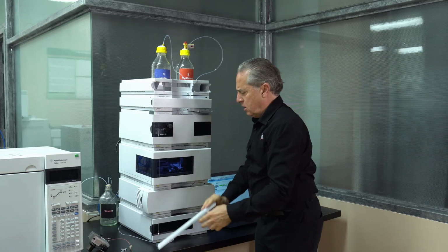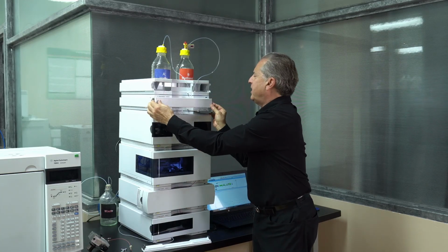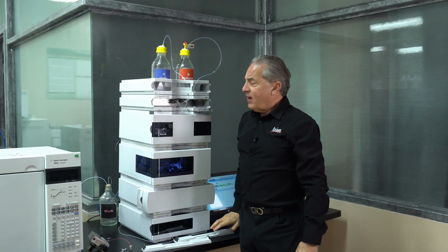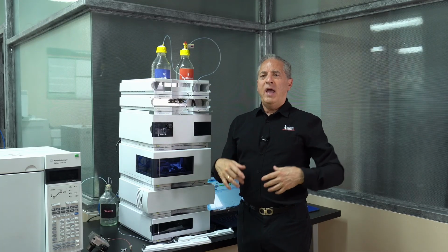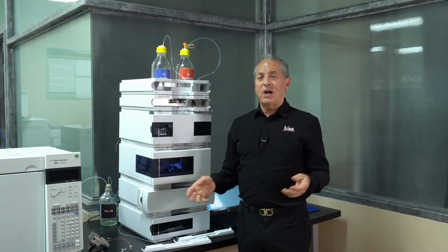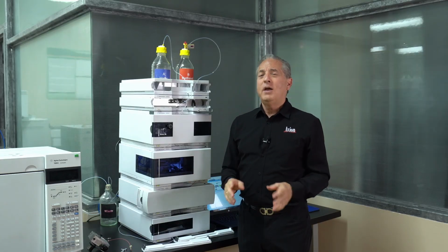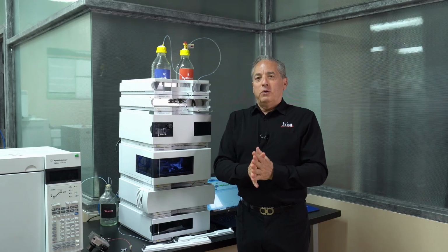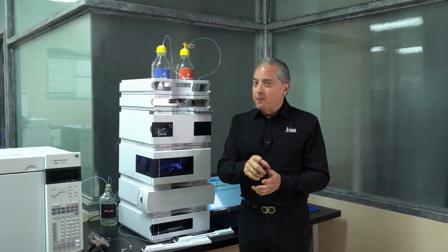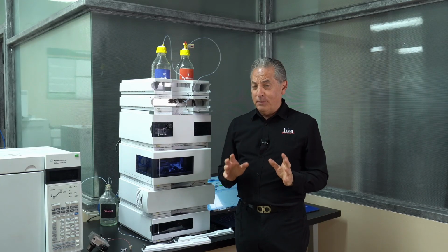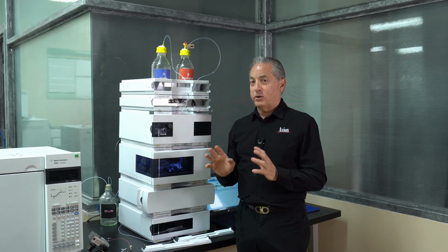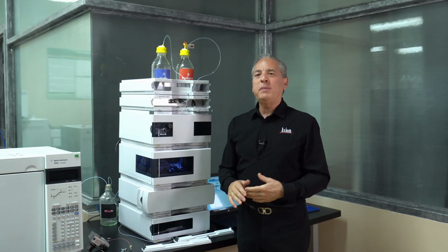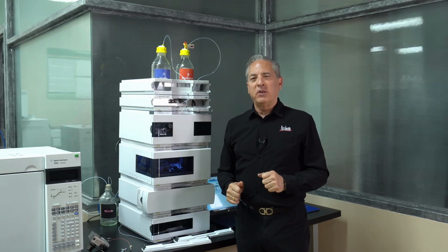So I showed you before that we go in the degasser. And the degasser is a very simple device, with a vacuum pump in there. And I always say you plug it in, turn it on, and it works forever. It never goes bad. Well, the only thing you could do to make it go bad, and this is on you, I'll tell you the most common thing people do to break their degasser. So please do not do this. And that is they precipitate buffer inside one of the channels.